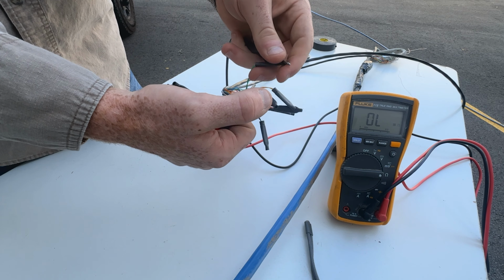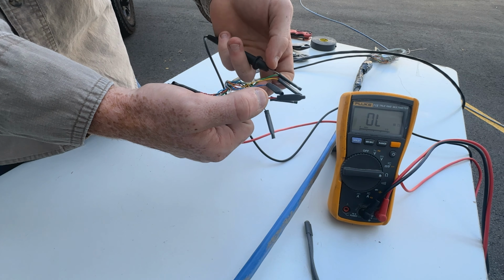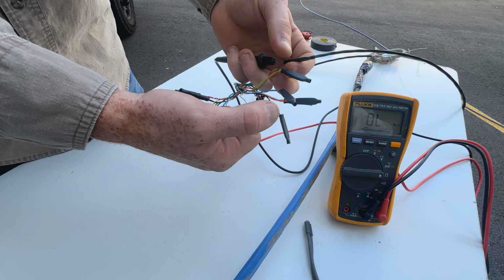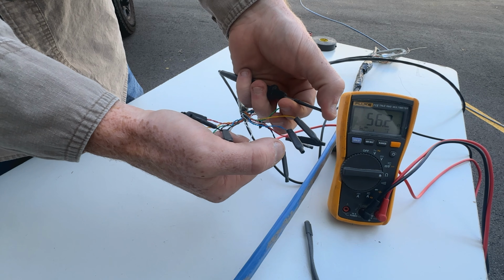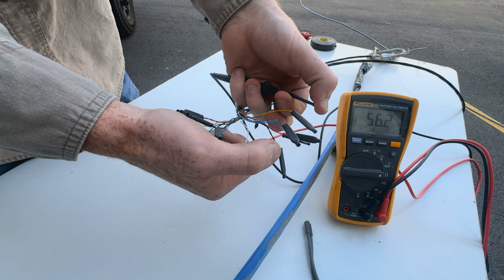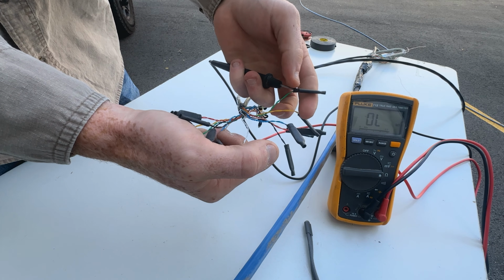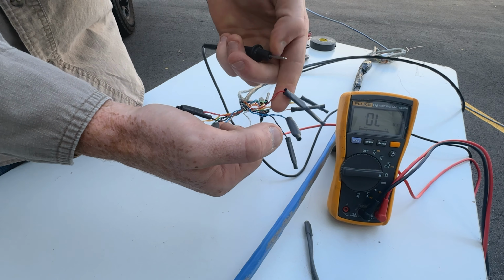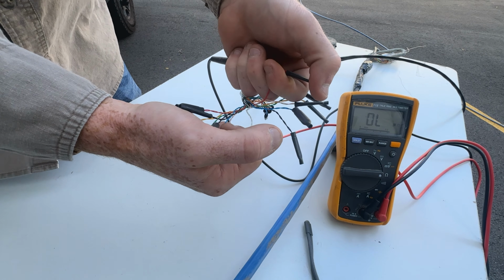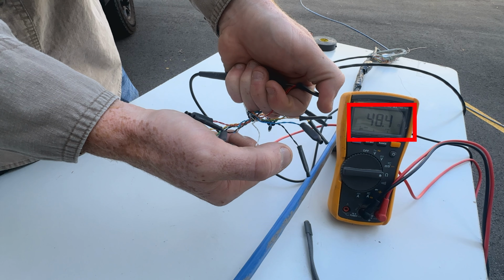Next, we can test the green wire. Now we can see a steady number of 56.2. As you work your way up the cable, these numbers should decrease between about 5 and 10 each time depending on your cable type. Next, the red wires. A steady 48.4 means this thermocouple is good as well.